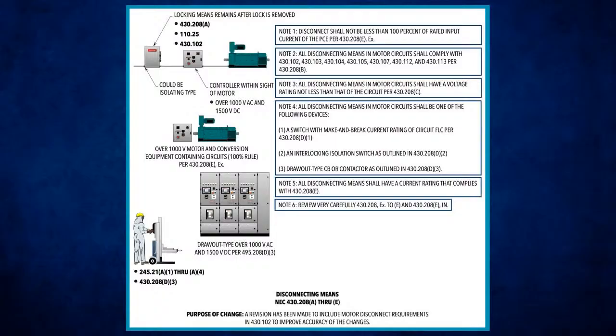The other important thing to point out is the current rating. Those disconnecting means for motor circuits are required to have a current rating not less than the overload trip current setting. True, okay.